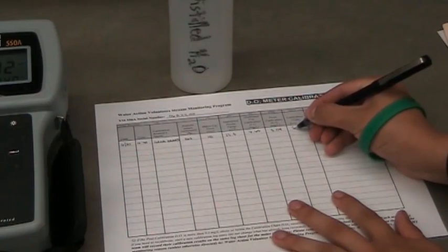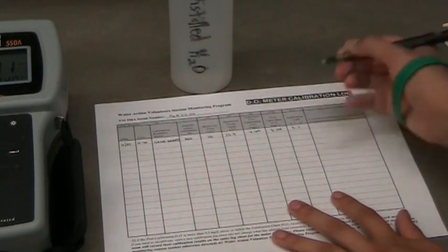If the difference between your calibrated value and the value on the chart is greater than 0.3 milligrams per liter, recalibrate the meter before use. Leave your meter on after calibration until you are finished collecting data for the day. If an error appears during the calibration process, see the video for changing the tip on the DO sensor. If calibration still does not work, contact your local WAVE coordinator.